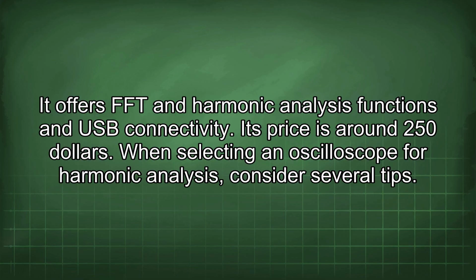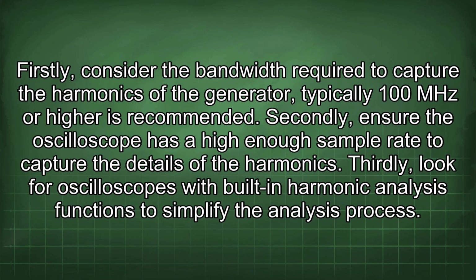When selecting an oscilloscope for harmonic analysis, consider several tips. Firstly, consider the bandwidth required to capture the harmonics of the generator. Typically 100 MHz or higher is recommended. Secondly, ensure the oscilloscope has a high enough sample rate to capture the details of the harmonics. Thirdly, look for oscilloscopes with built-in harmonic analysis functions to simplify the analysis process.